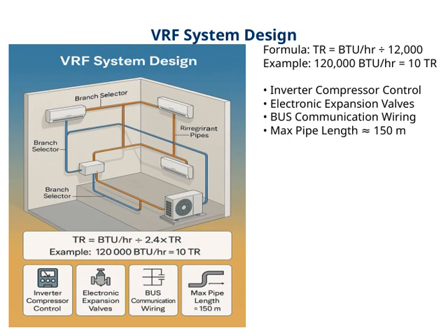We also need to consider the bus communication wiring, which connects all the system components for seamless control and monitoring. This wiring is essential for integrating the system and enabling smart system management. Lastly, the maximum pipe length is approximately 150 meters.